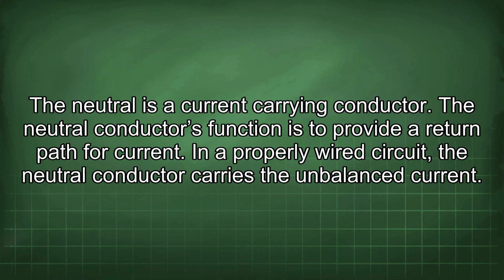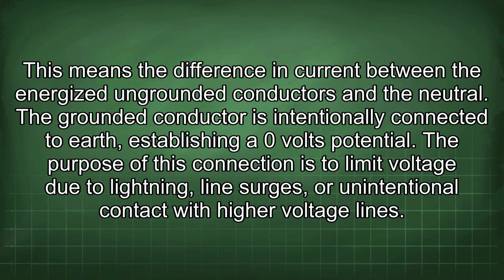The neutral is a current carrying conductor. The neutral conductor's function is to provide a return path for current. In a properly wired circuit, the neutral conductor carries the unbalanced current. This means the difference in current between the energized ungrounded conductors and the neutral.